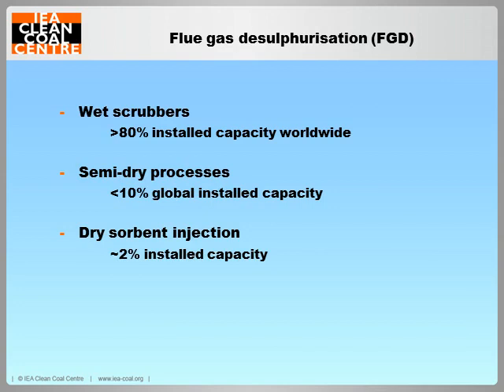There are a wide range of commercial FGD processes available for removing sulphur oxides from flue gas, and I can categorise these by their water usage into wet scrubbers, semi-dry scrubbers and dry systems. And wet scrubbers are by far the most common system, with over 80% of installed capacity worldwide.